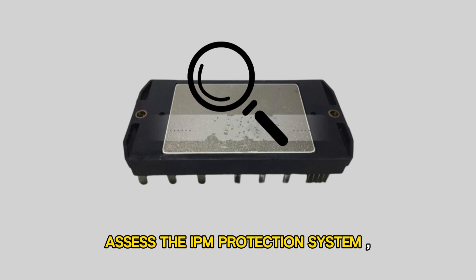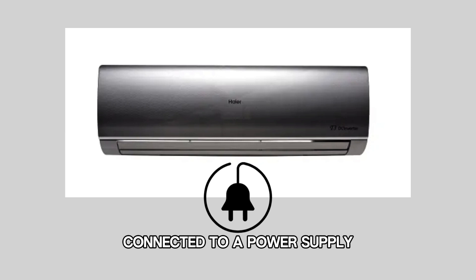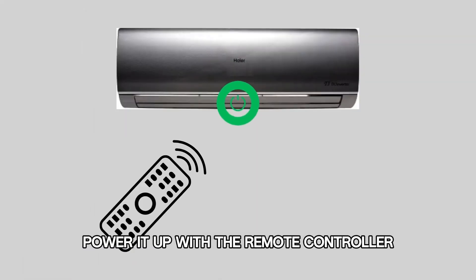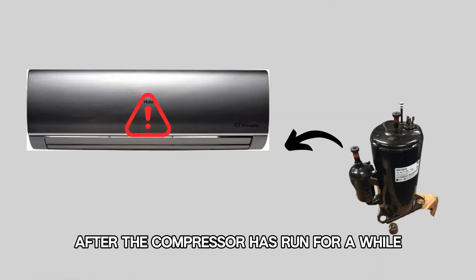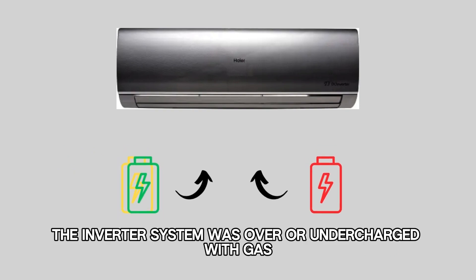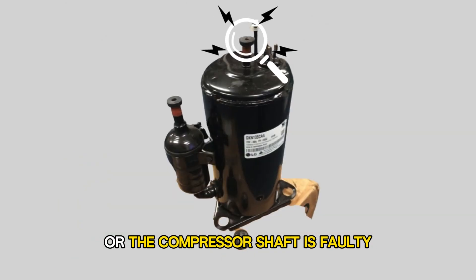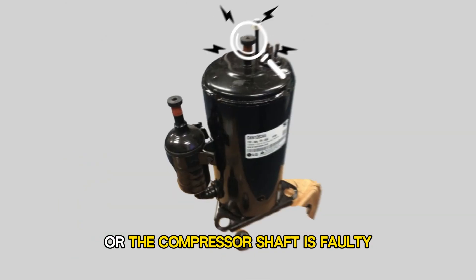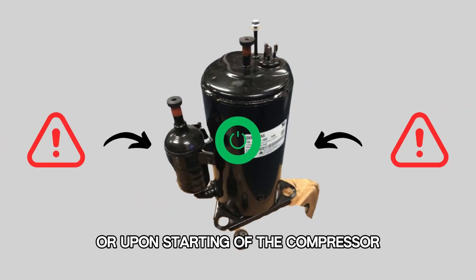Assess the IPM protection system. With the Haier DC inverter connected to a power supply and in standby mode, power it up with the remote controller. If the error code is reported after the compressor has run for a while, then the inverter system was over or undercharged with gas, or the compressor shaft is faulty, necessitating compressor replacement.